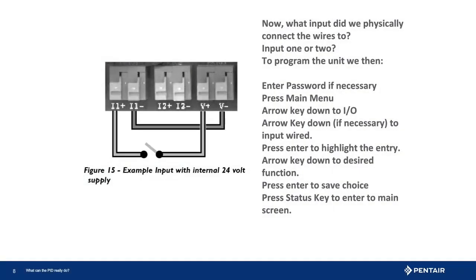We connect the safety, now to program the drive. To do so, you may need to enter the password. This can be found in the owner's manual unless it has been modified. Once unlocked, go into the main menu by pressing the menu key. Arrow key up or down until you find I/O and press enter. Next, scroll until you see what you are programming. In this case, we connected the control to input 1 and press enter. Now we want the pump to stop pumping when the current is present. So, we would use the external fault setting. And with that we have connected an input and programmed it and are ready to run the control.